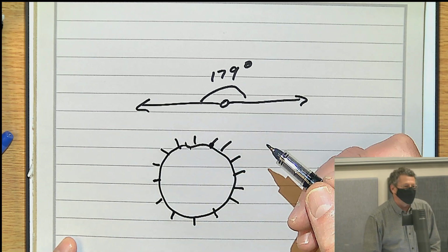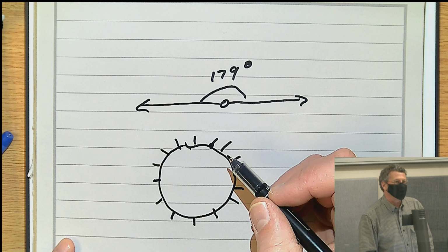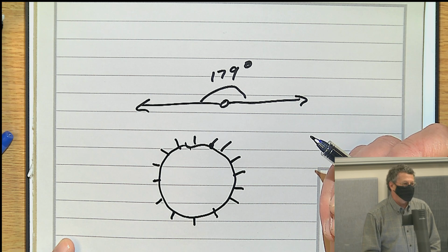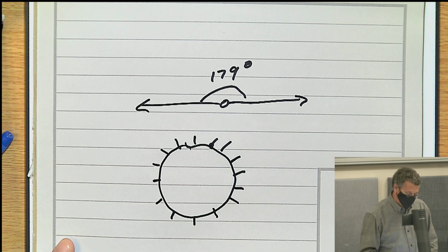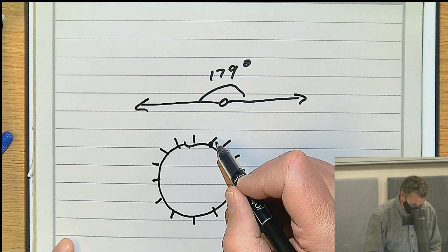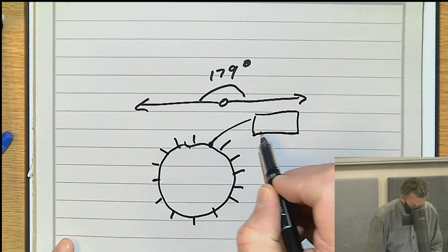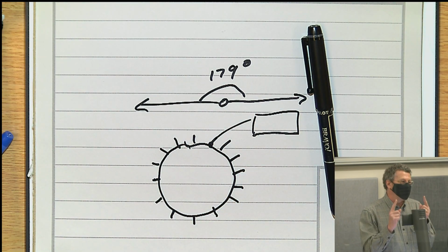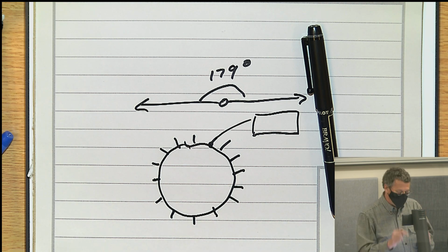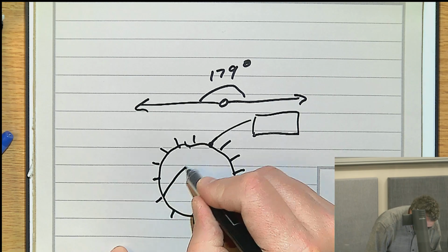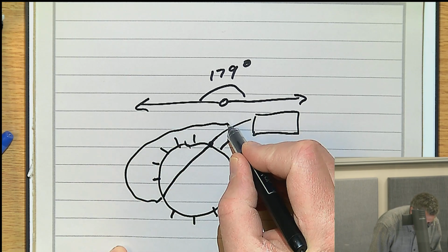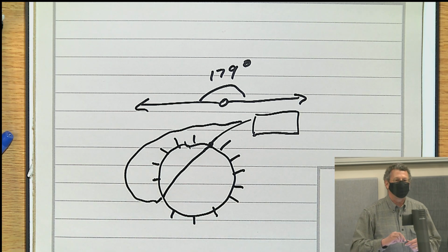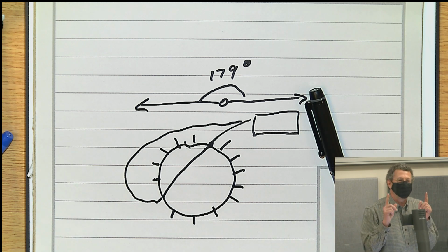And this is really cool. They have this high-speed electronic circuitry that detects when the photon was detected, within nanosecond accuracy. Then they put it in what's called list mode, and they have a process that takes all this data and does a kind of matchmaking. So it finds photons that arrived at the same time. If two photons arrived at two different detectors at the same time, you assume they must have come from the same underlying event. When I say same time, I mean within 10 nanoseconds. That's called a coincidence window.